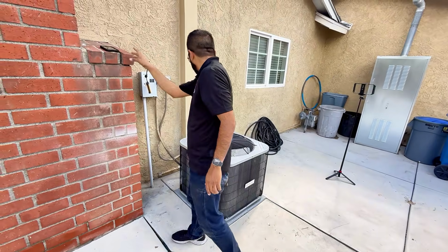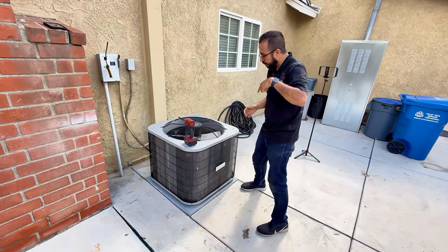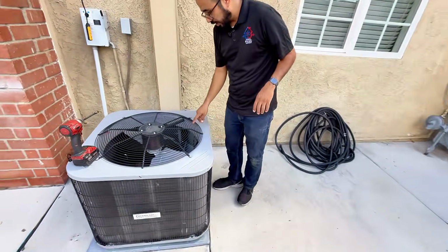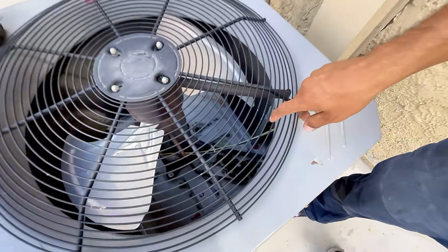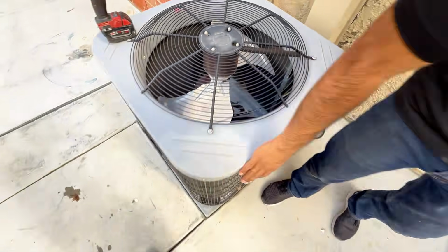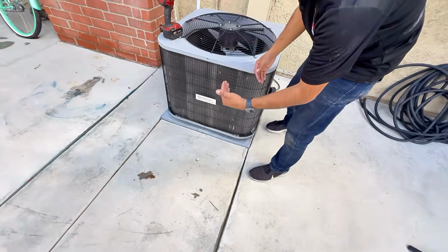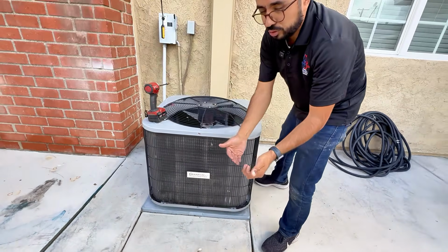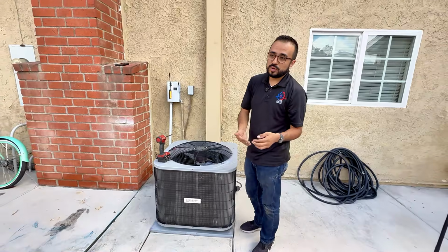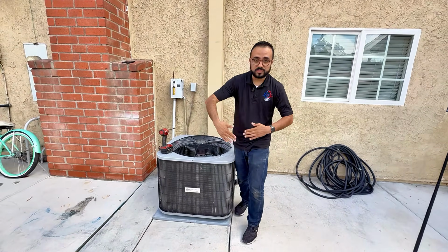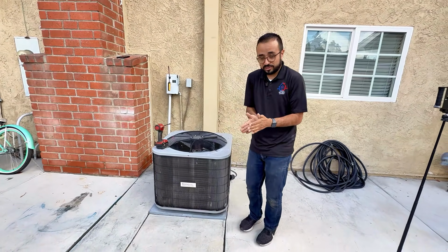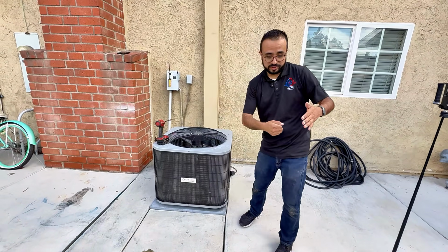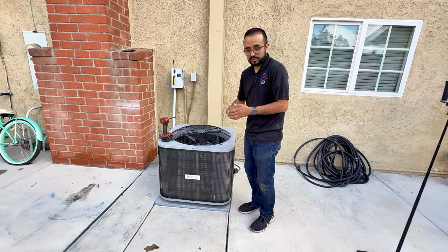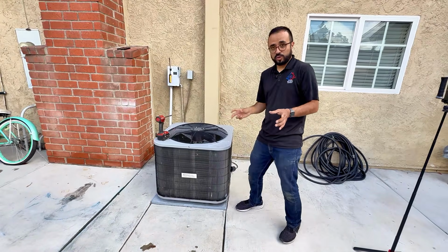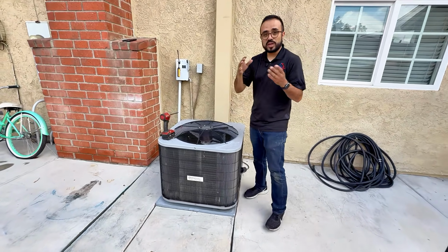So doing the maintenance outside, if you come a little closer, you see inside there's a little bit of leaves. It's a little dirty, right? Also here, this isn't too bad. Your outdoor coil, you have to wash it from the outside in and inside out. In commercial, you're dealing with two pieces of condenser coils. Those you have to separate and clean from the inside, then inside and out, and outside and in on both coils. But this one is just one, so we don't have to do any of that.